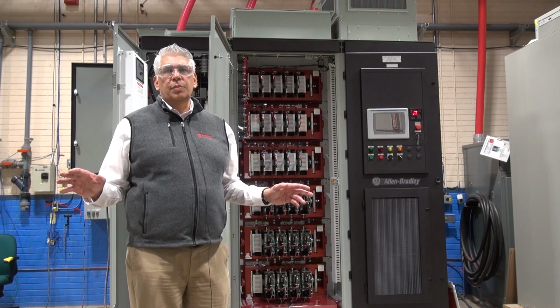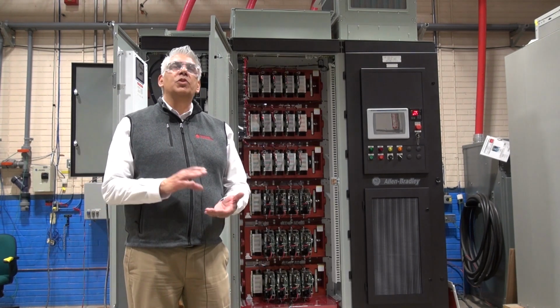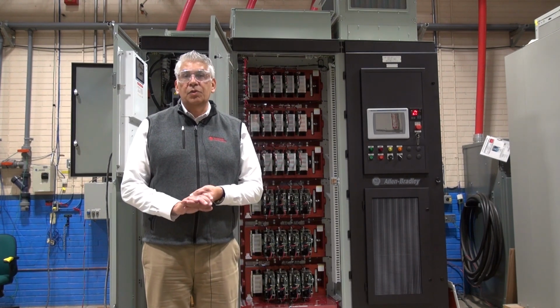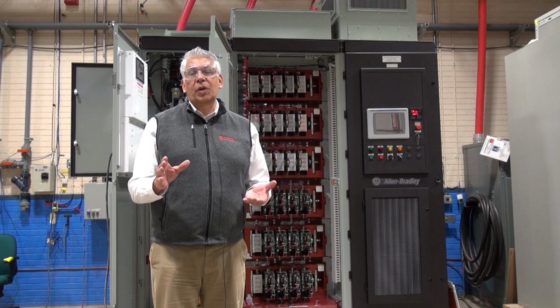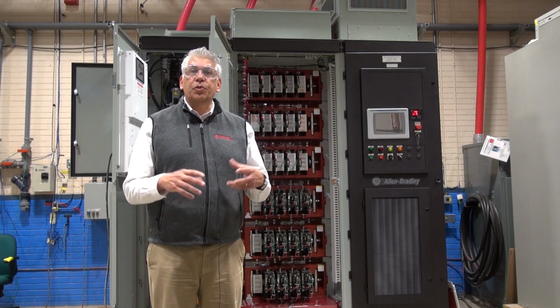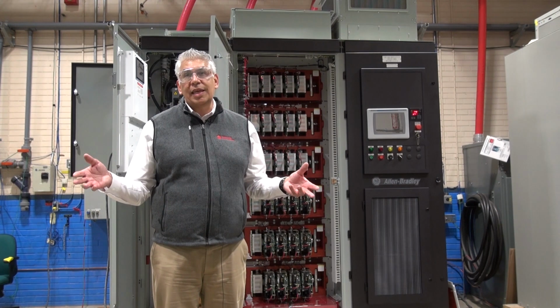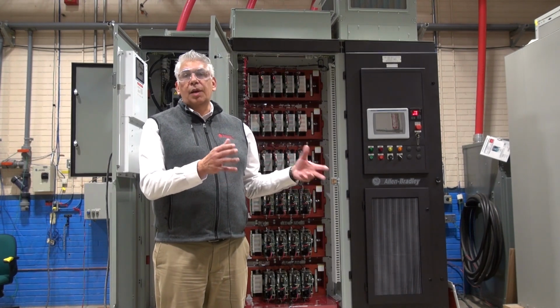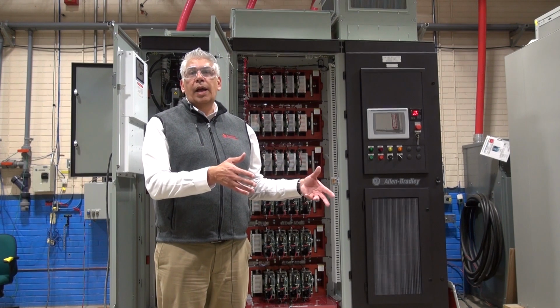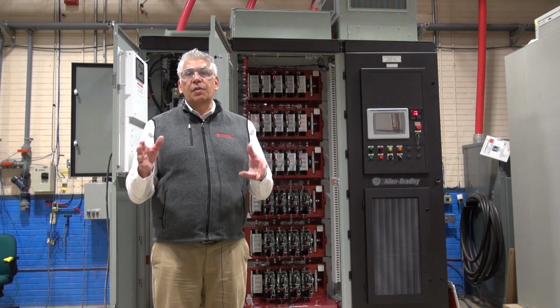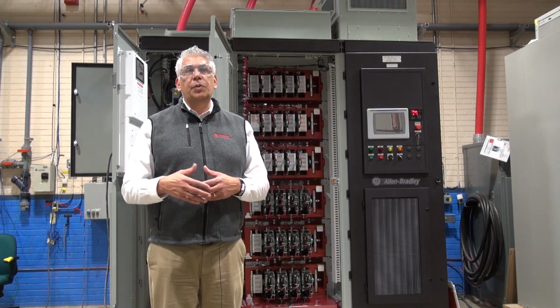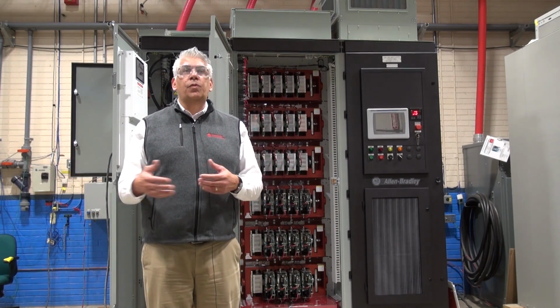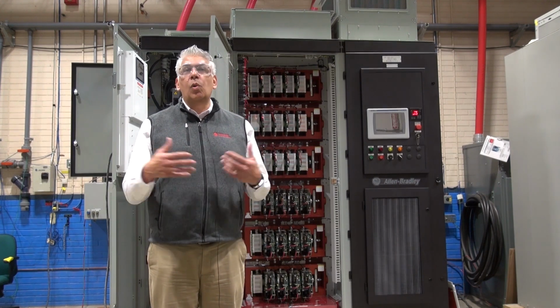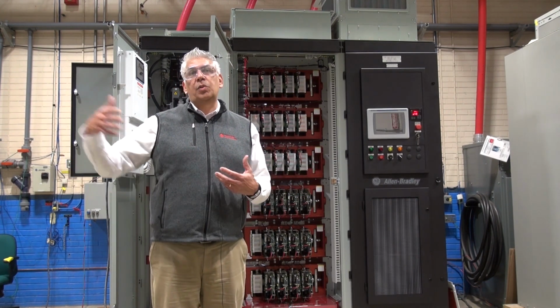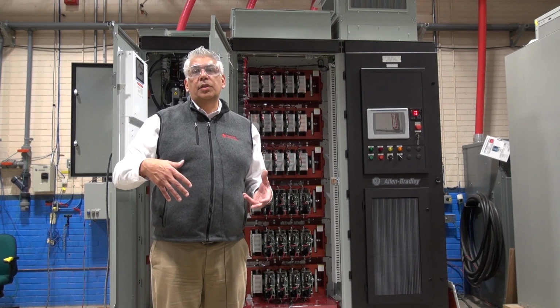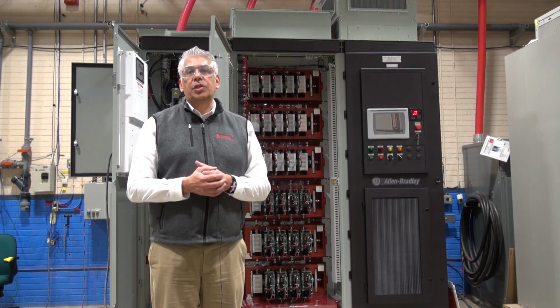Just as an overview, the PowerFlex 7000 is available from 2300 volts to 6600 volts, from essentially zero all the way up to 720 amps. We offer 3 different frame sizes, an A, B, and C. An A-frame is optimized for small size and lower power air-cooled versions. Then we have a B-frame for higher power versions, and a C-frame, or liquid-cooled, for marine applications and a wide variety of applications where customers potentially want to reject a lot of the heat out of the particular control room to reduce air conditioning costs.